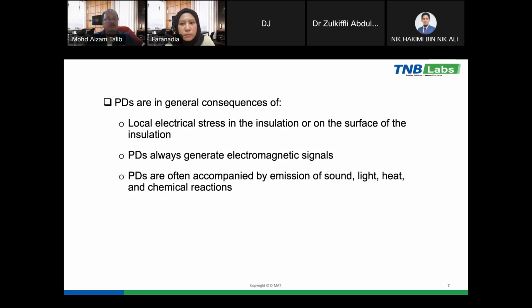In general, the PD is a consequence of the local electrical stress in the insulation. So, when we have the insulation, it can cause the partial discharge due to the electrical stress, or on the surface of the insulation. The partial discharge can also happen due to the stress on the surface of the insulation. And partial discharge always generates an electromagnetic signal. That's why we can detect the partial discharge from the electromagnetic wave, and the presence of partial discharge will also generate sound, light, heat, and chemical reactions.